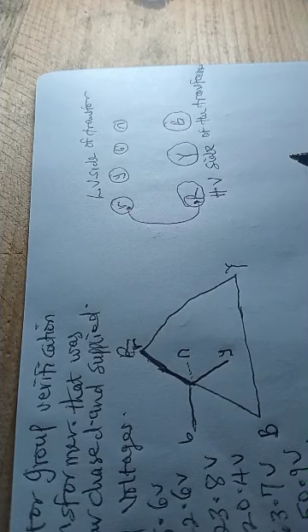So you will now apply red, yellow, blue phase voltage across this red phase, yellow phase, and blue phase. Face to face, and face to face. So this is 415 volts. Between here to here, also 415 volts. Then between here to here, 415 volts also, meaning red, yellow, yellow, blue, and blue, red. So you apply line 1, line 2, line 3 voltage on the high voltage side of the bushing.